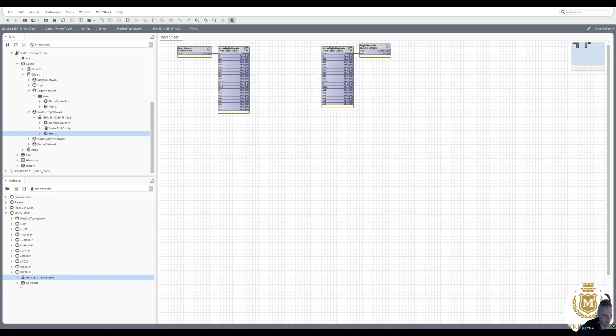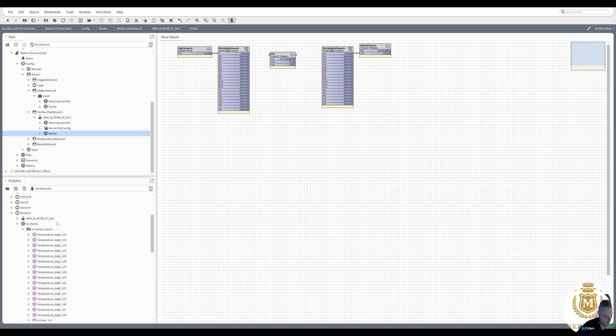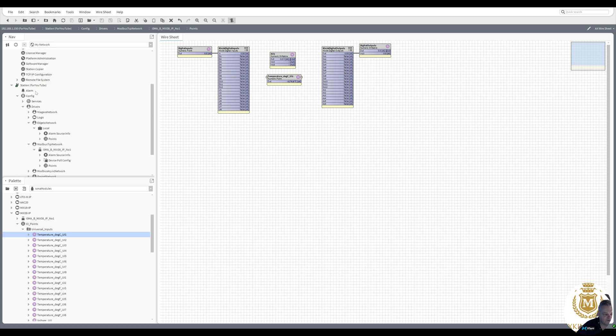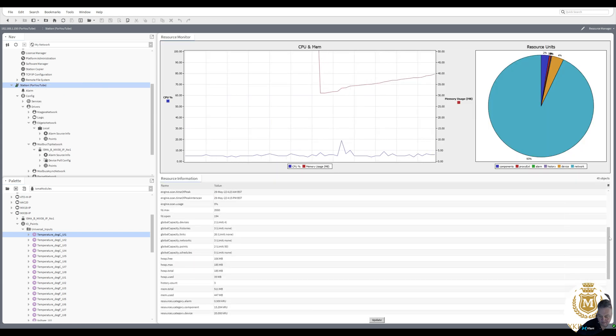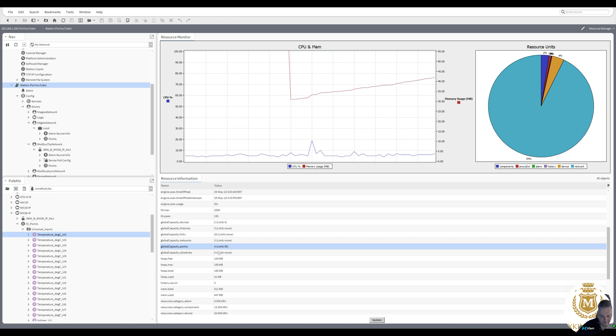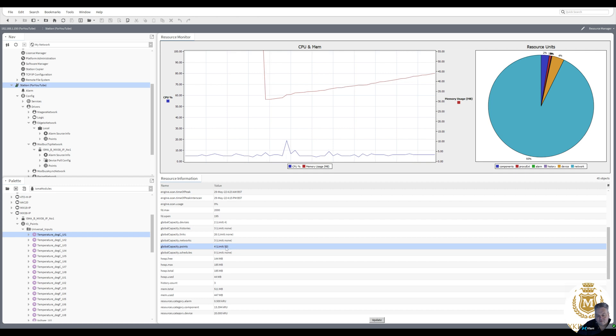As soon as I start adding extra points on the Mix 38, that count goes up. For example, going to the wire sheet of the Mix 38 IP and adding analog output one — that's now going to show three points used. Then going to universal inputs and adding a temperature for UI 1, that's now four points used. Back in the resource manager after updating, we've got four points out of the 50.